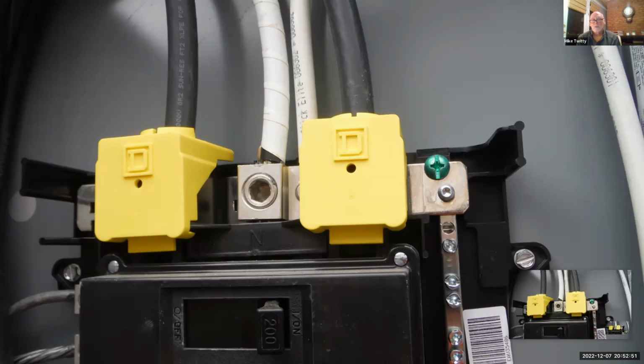You don't want to see sheet metal screws or anything like that. That's a listed screw that goes in there. Now, if you want to use this panel as a sub panel, that screw comes out and some changing goes on as far as where your equipment grounds and your neutrals are connected. We'll get into that in a little bit, but that's a main bonding screw, though the code calls it a main bonding jumper.